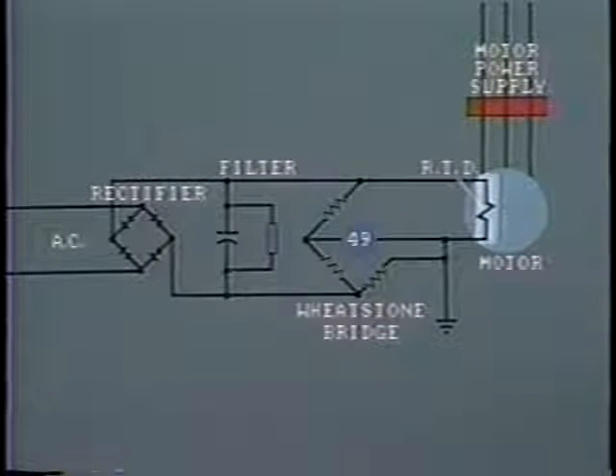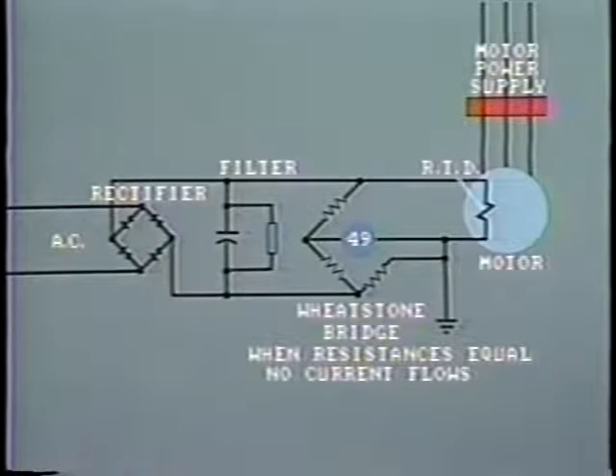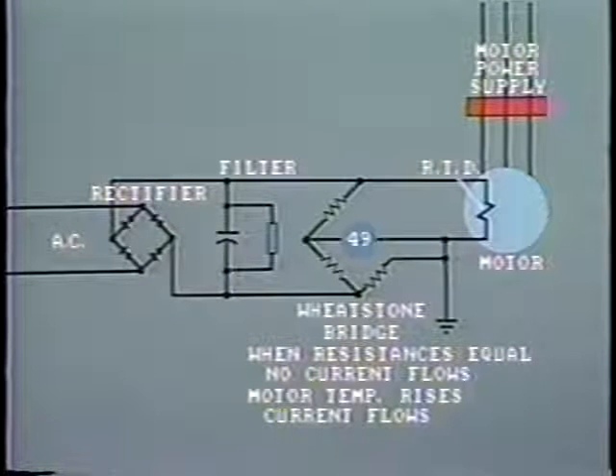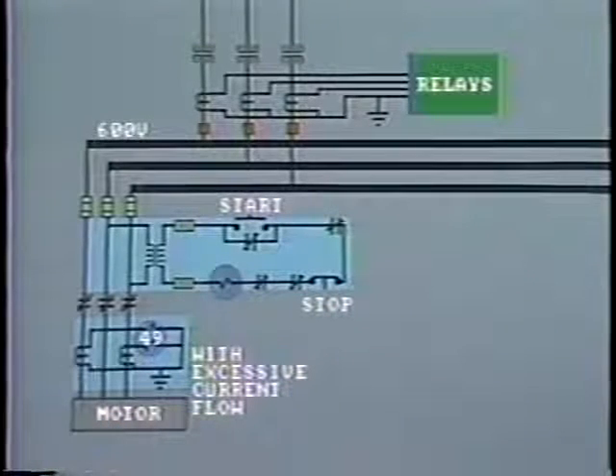The resistance detector forms part of a bridge circuit where the other three resistances are of known value. The bridge is supplied with current from a rectifier. When all of the resistances are of equal value, there is no current flow through the temperature relay, number 49. However, as the motor temperature rises and the resistance of the detector increases, the balance of the bridge will be upset and current will flow through the relay and cause it to operate at a predetermined set point. In the contactor circuit, which we have been studying, this would open these contacts and so de-energize the contactor coil.